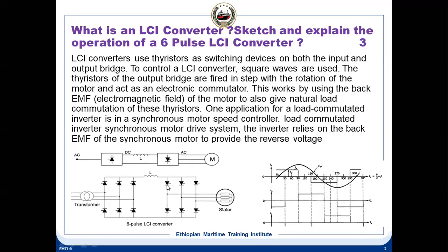It is being fired using a control circuit, and what we will do is convert this DC, this square wave pulse, into an AC. It will be fired like this. You see the square pulses are coming. It will give a fluctuating DC or a sine AC like this. So the output will be like this. This works by using the back EMF of the motor to give a natural commutation.